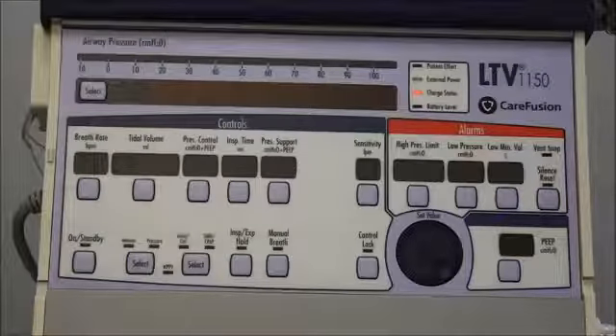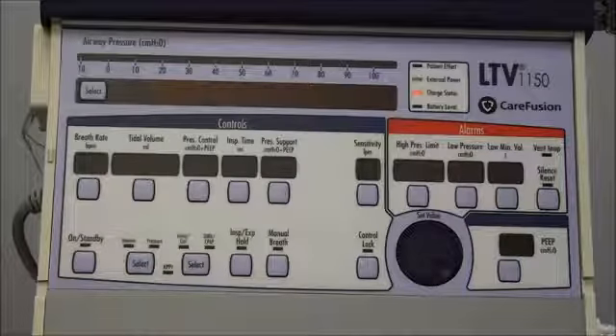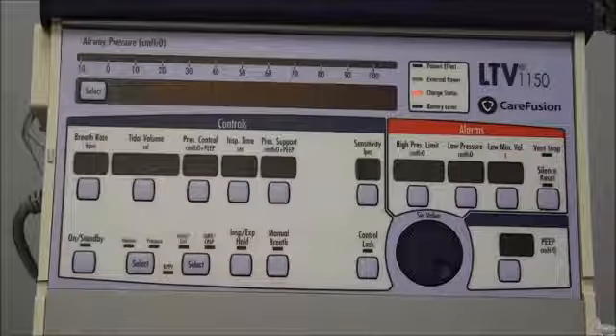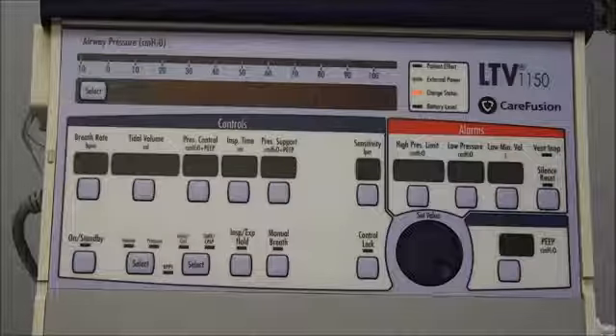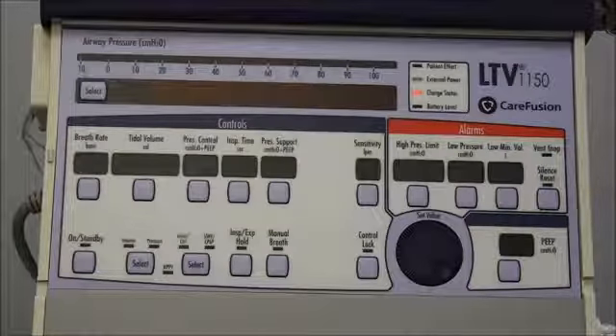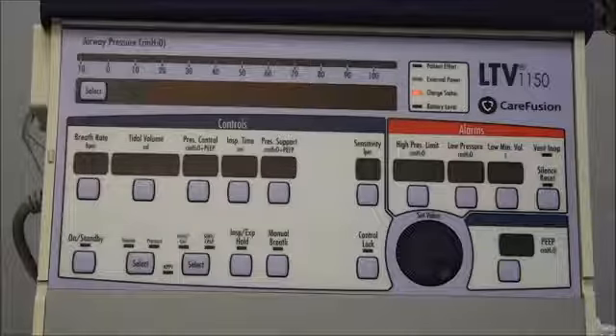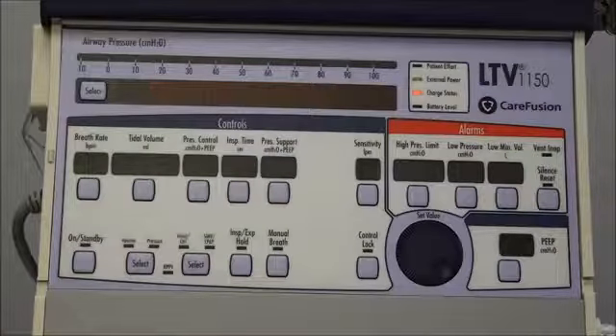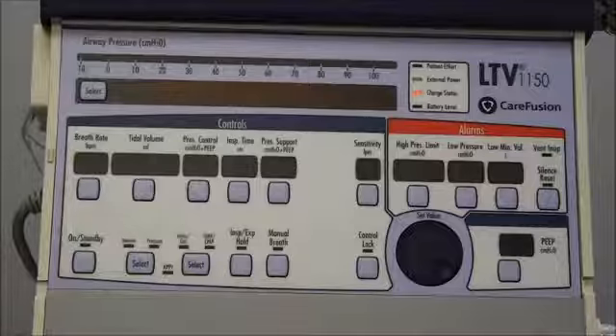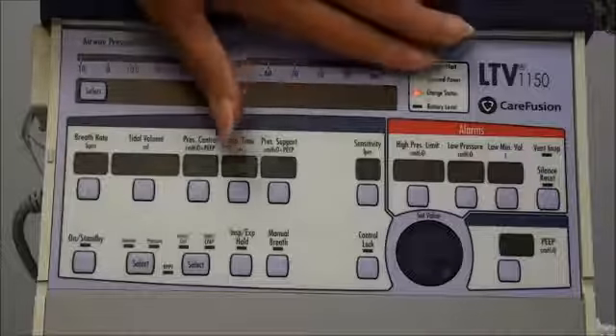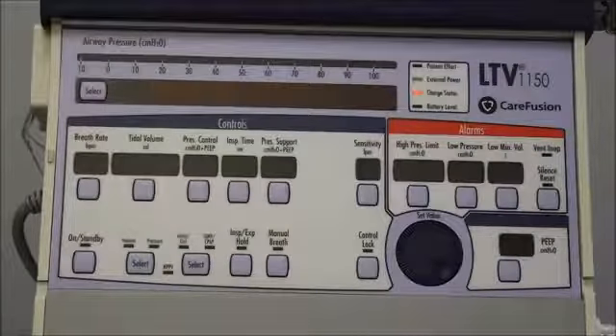It will also light up green if you have it plugged into an external battery, because those are both external power sources that is being used to power the ventilator. This ventilator also has an internal battery. So if you have it unplugged from the wall and unplugged from the battery, this external power light will be off, and it will be running on its internal battery.